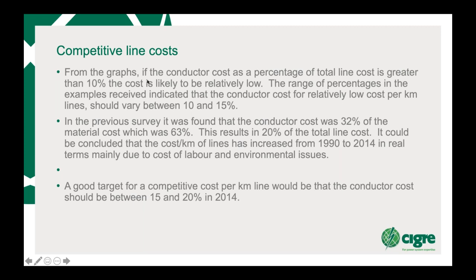So from the graphs, if the conductor cost as a percentage of total line costs is greater than 10%, the cost is likely to be relatively low. What we did in the actual brochure, you can get all the details. But really what you're looking at here is, what is your conductor cost? And is the conductor cost greater than 10% of the total line cost? If so, you can be fairly happy with the overall cost of the line. The range of percentages for conductor cost for a relatively low cost per kilometer should vary between 10 and 15%.